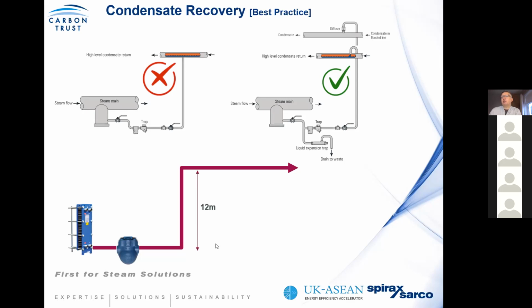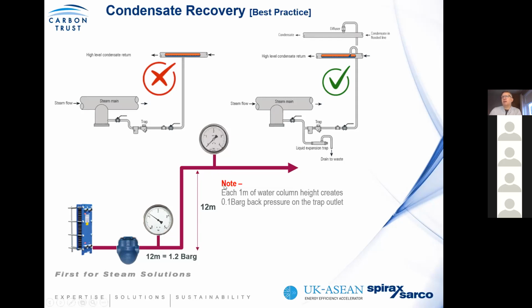In this case example here, let's consider that we're rising 12 meters back up through this header into our main header. However, what we should understand is that each 1 meter of water column height creates 0.1 bar back pressure on the trap outlet. So in this scenario here, on our pressure gauge, if there is no operation, you'll find that this pressure gauge would basically indicate 1.2 bar. If we go to the top of our steam condensate header, our pressure gauge will show us 0 bar, because if this pipe interconnects to an atmospheric pressure condensate recovery unit and drops under gravity, then we should be at a 0 pressure system.